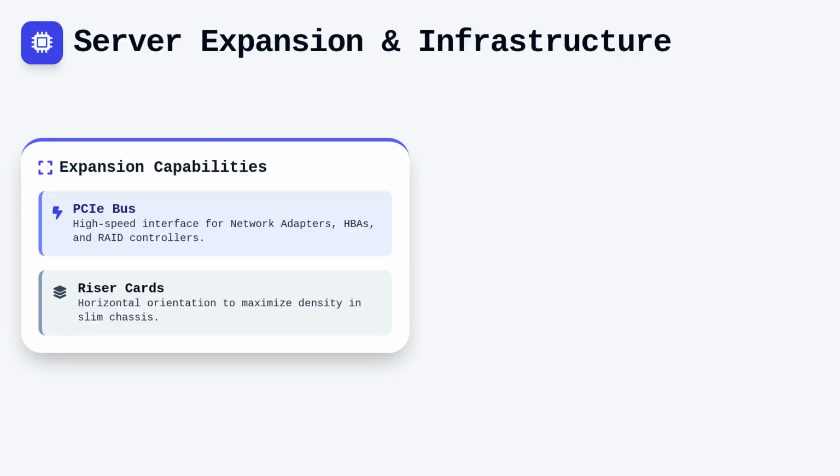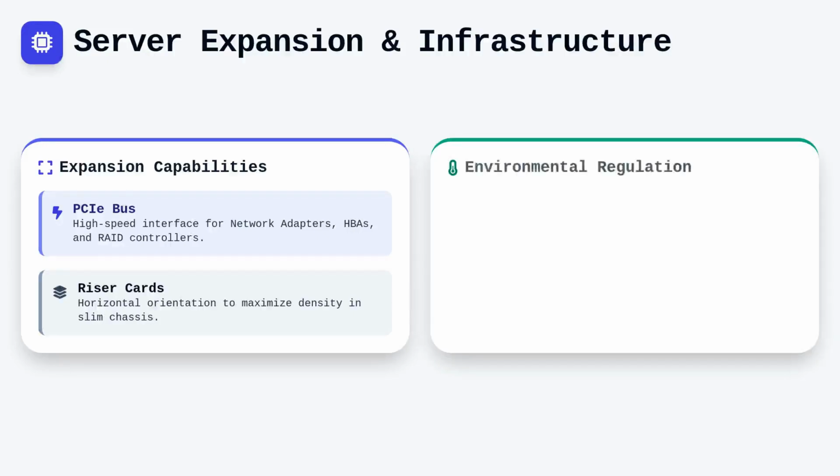Beyond the hardware itself, the surrounding environment must be strictly regulated to prevent premature equipment failure. HVAC systems maintain specific temperature and humidity ranges to avoid both electrostatic discharge caused by low humidity and potential oxidation or cooling inefficiency in overly humid conditions. Hot and cold aisle containment strategies prevent the mixing of air, ensuring that cool air is directed solely through the front of the intake side equipment.